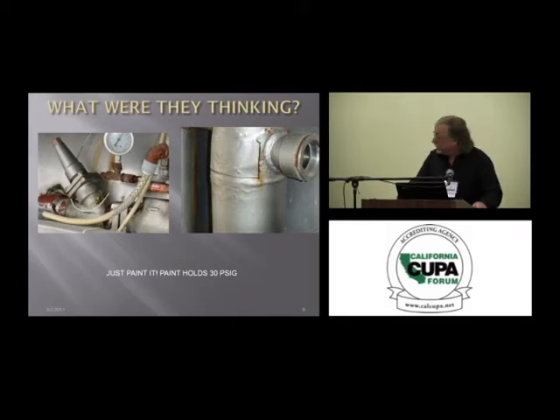This happens, yeah, you're not even going to see this one. This is a picture of a component with the whole side blown right out, and it's called hydrostatic expansion. This is where they were not doing correct maintenance on a liquid line, and they installed an additional valve that shouldn't have been in that line. It was a check valve. It should not have been in there. Hydrostatic expansion occurred, and it ruptured the side of the equipment right out.